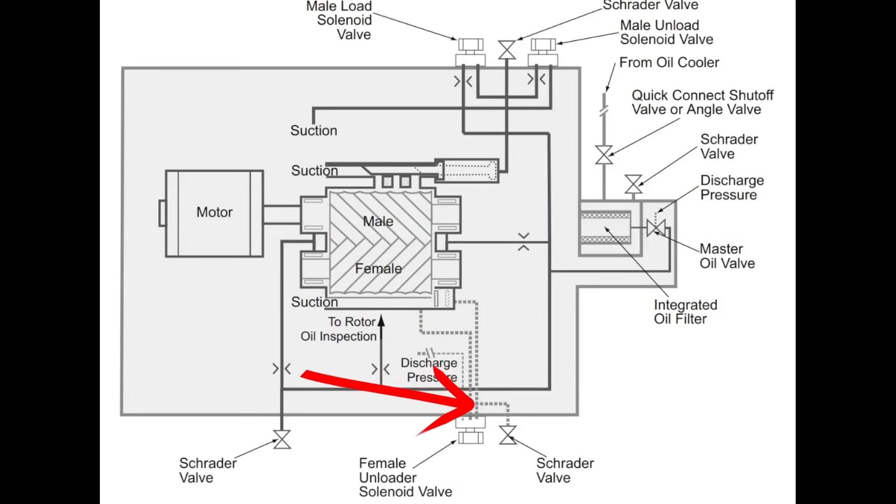So let's start with the female unloader. A female unloader is used at the startup cycle. So when the compressor is first started up, the female unloader is de-energized. This valve here is allowed to move, and we can bypass discharge gas back to suction.